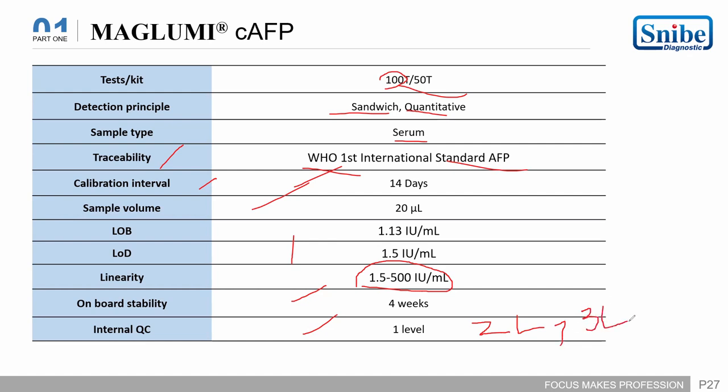So they can use Randox or Bio-Rad third party QC, or ICAS third party QC for alpha fetoprotein as multi constituent analytes. Especially Randox and ICAS give a solution as multi analytes, so with those they can run multi analytes on Maglumi. But SNIBE is providing a solution from our platform: we give a free of cost calibrator and control with the reagent.